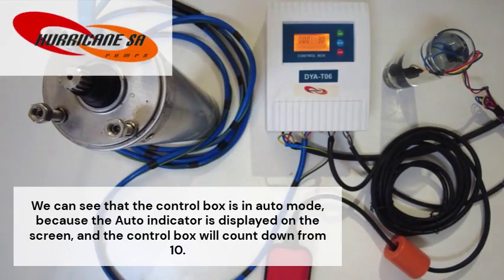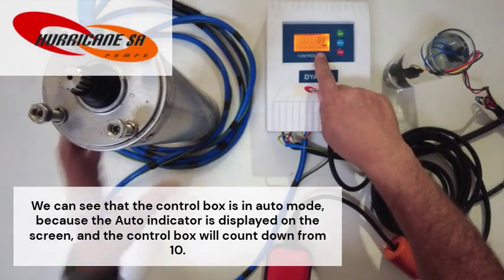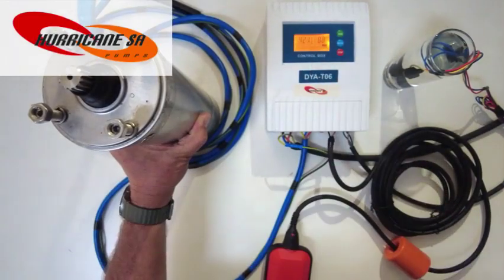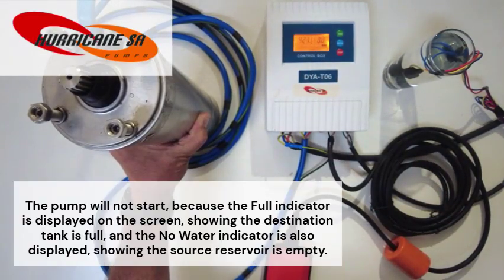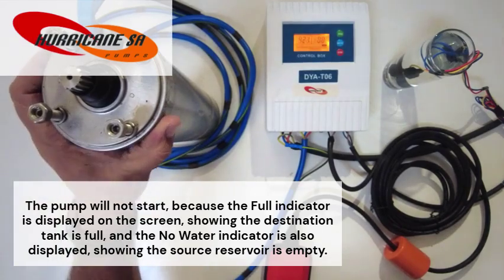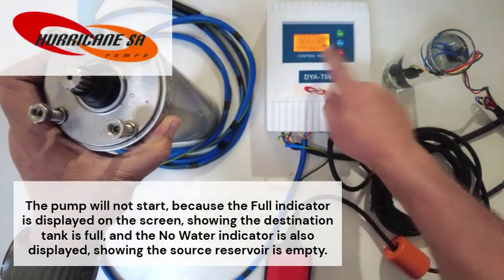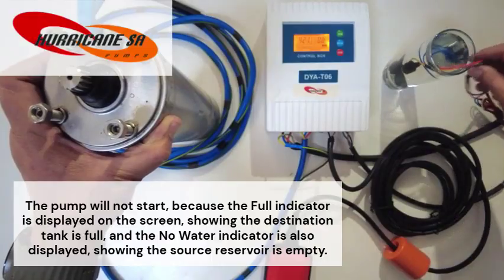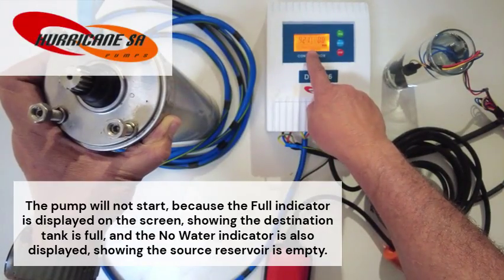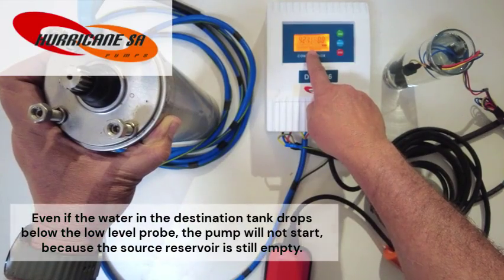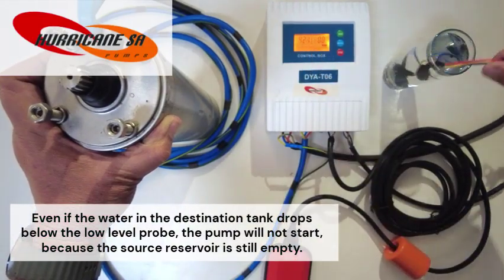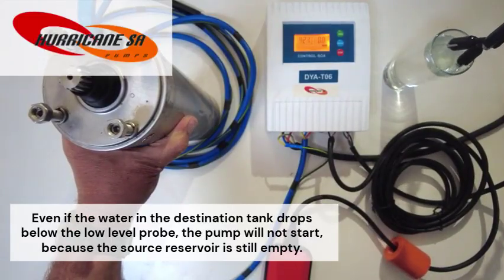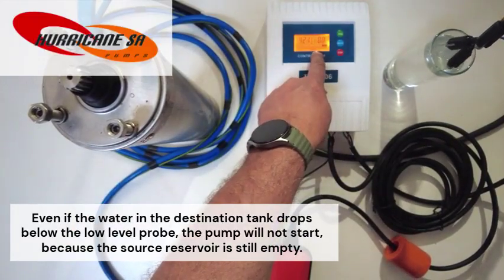We can see that the control box is in auto mode because the auto indicator is displayed on the screen, and the control box will count down from 10. The pump will not start because the full indicator is displayed on the screen, showing the destination tank is full, and the no water indicator is also displayed, showing the source reservoir is empty. Even if the water in the destination tank drops below the low level probe, the pump will not start because the source reservoir is still empty.